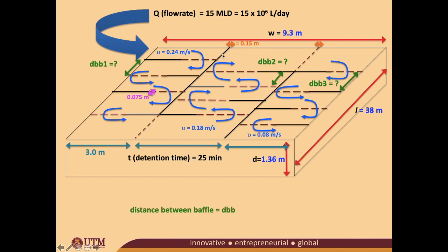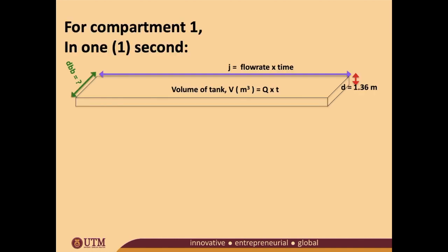Let's focus on one particular segment — the first segment of the channel, which I've highlighted with a black ring. That area shows the distance between baffles we want to find for compartment one. From our previous video, recall the diagram: j is the flow rate times time, this is the volume of the tank, and the depth is 1.36 meters, which has already been designed and won't change.